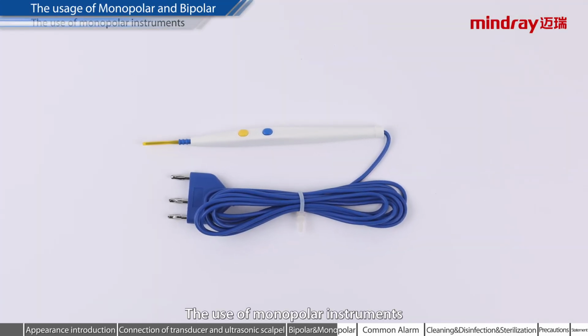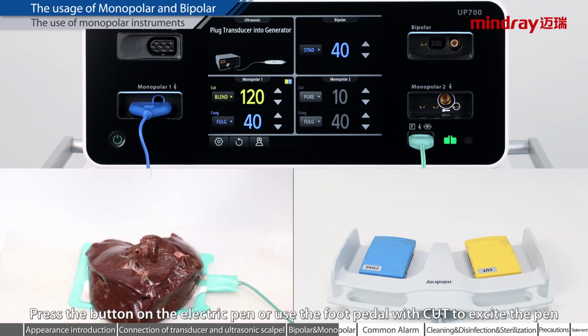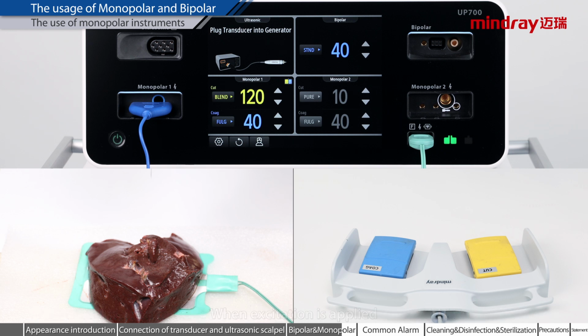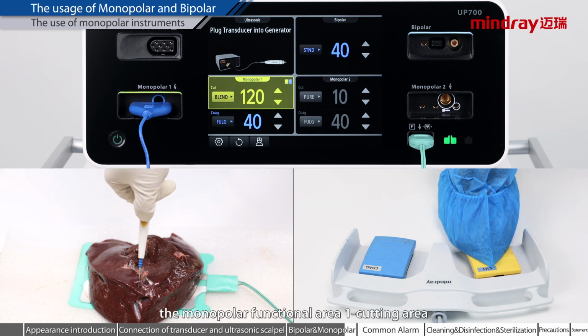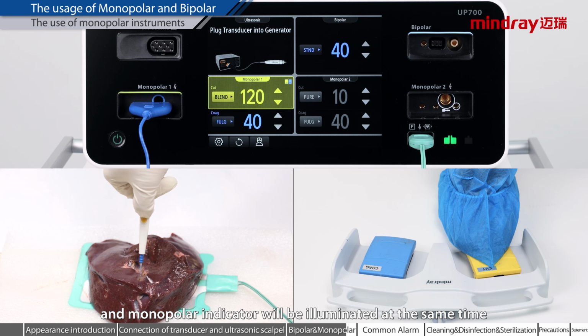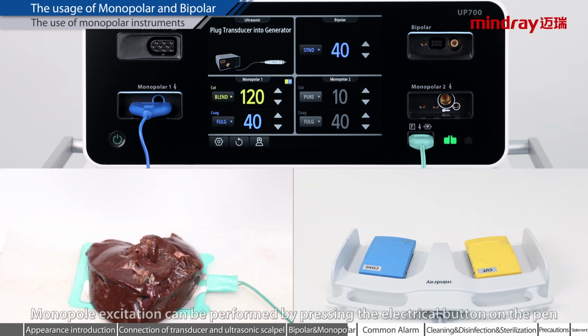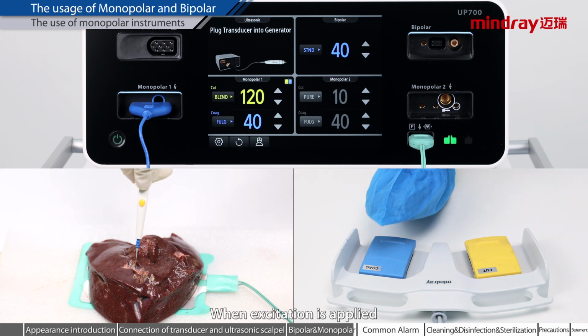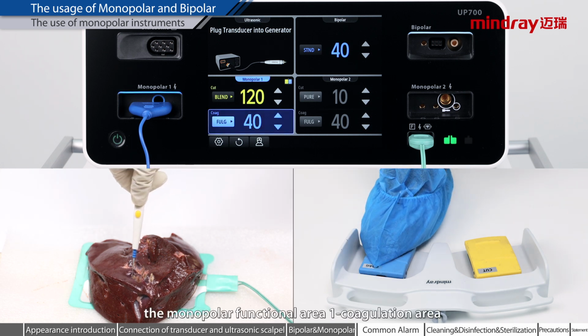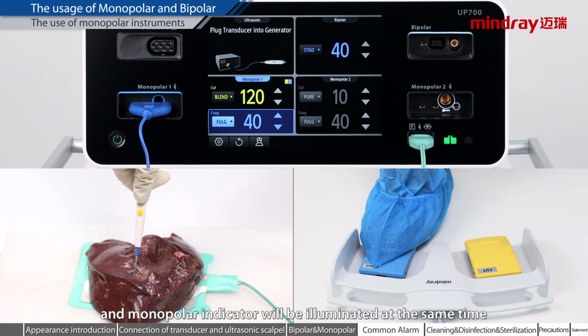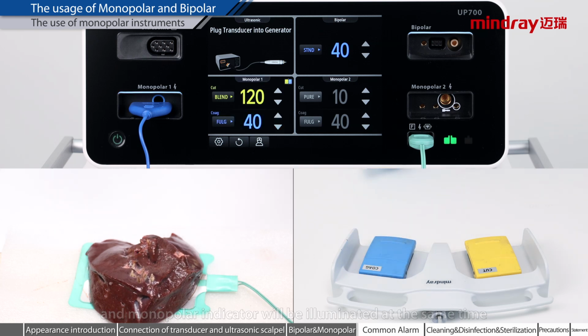The use of monopolar instruments. Press the button on the electric pen or use the foot pedal with CUT to excite the pen. When excitation is applied, the monopolar functional area 1, cutting area, and monopolar indicator will be illuminated at the same time. Monopolar excitation can be performed by pressing the electrical button on the pen or by pressing the foot pedal with coagulation. When excitation is applied, the monopolar functional area 1, coagulation area, and monopolar indicator will be illuminated at the same time.